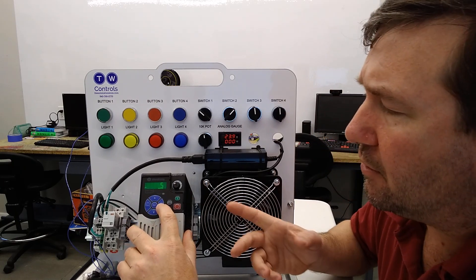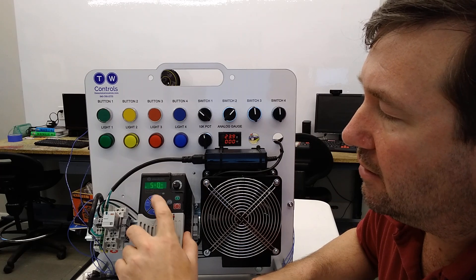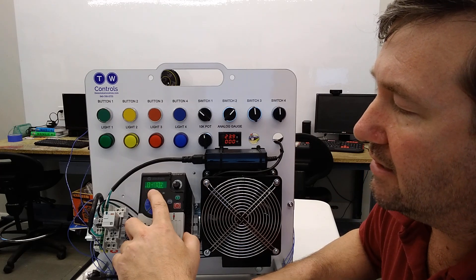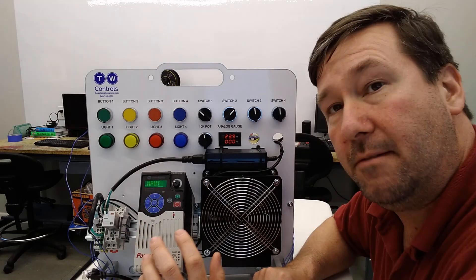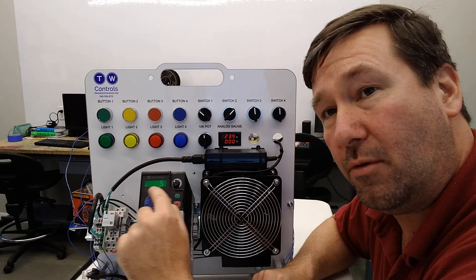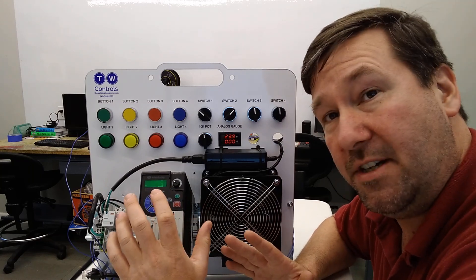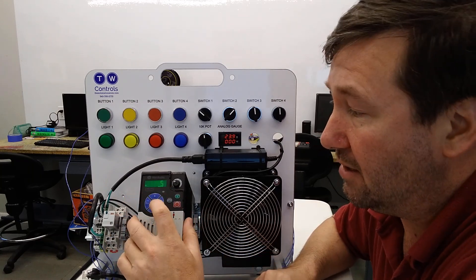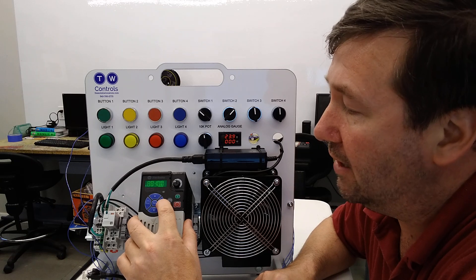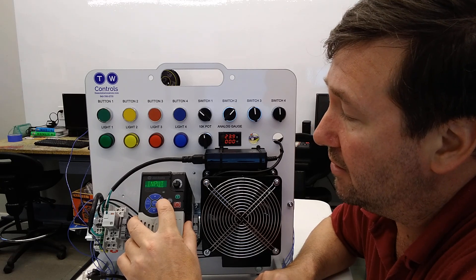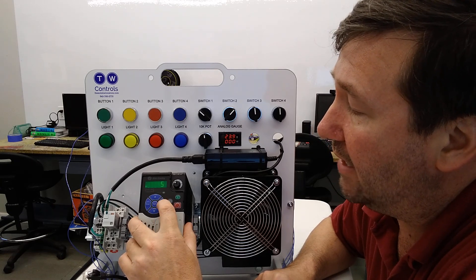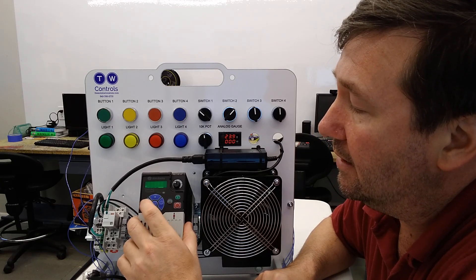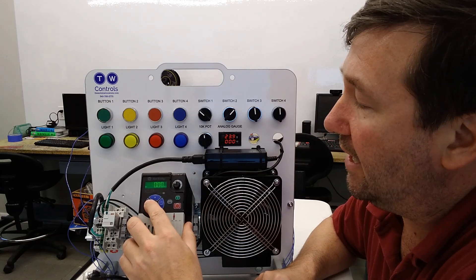And one thing, if you're not sure what these are, if you just sit here a second, it says five, zero to 10 volt input. So they have a nice scrolling feature that kind of gives you a quick description to make sure that you're on what you want. And that is what we want, is zero to 10 volt. We'll hit OK. And now we'll escape back out.